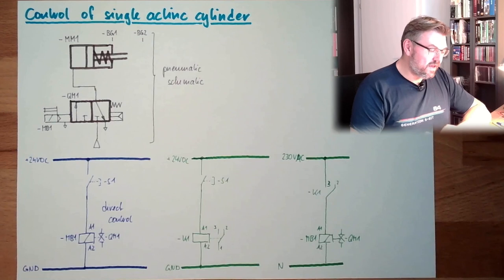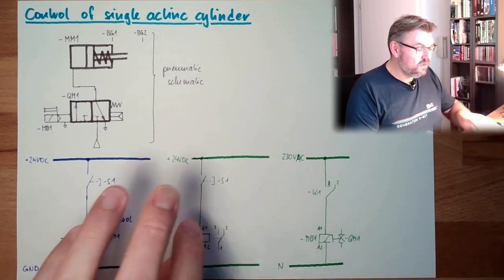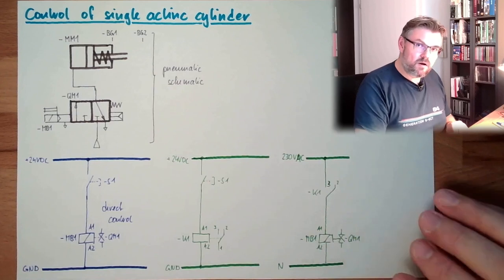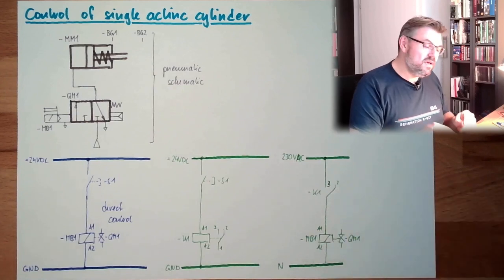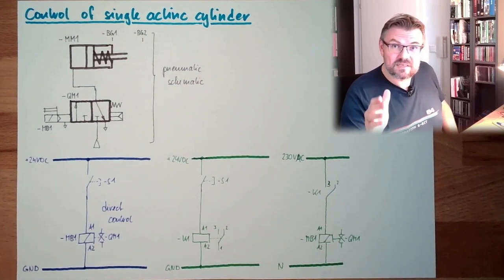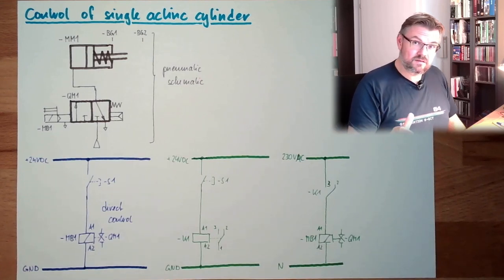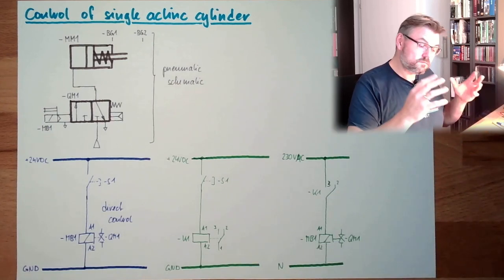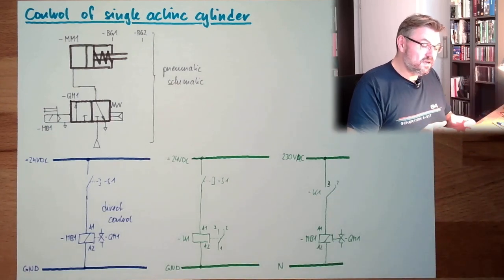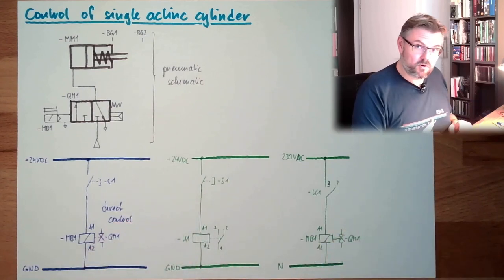And if the power somewhere you need more, then you should use this indirect approach. Also, in case of very complicated structures here, it is always a good idea to keep these complicated structures and logic apart from the part which is switching the power. Because then it's clear which relay, or even in that case might be a contactor, a big relay, a Schütz in German. If this is necessary, then you have to do it like that, indirect approach.